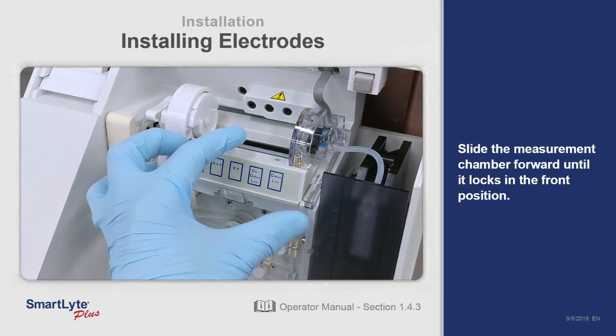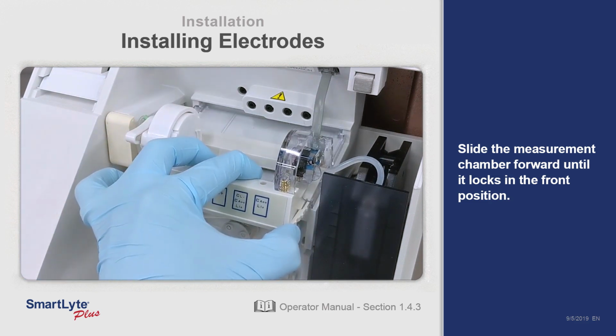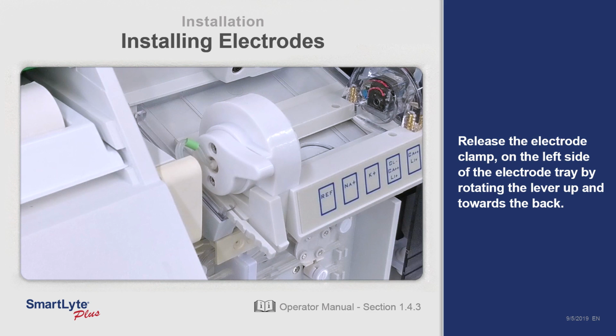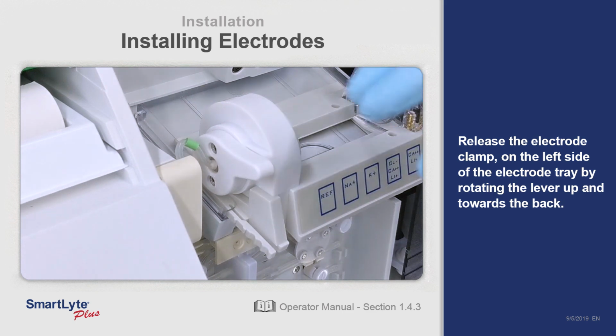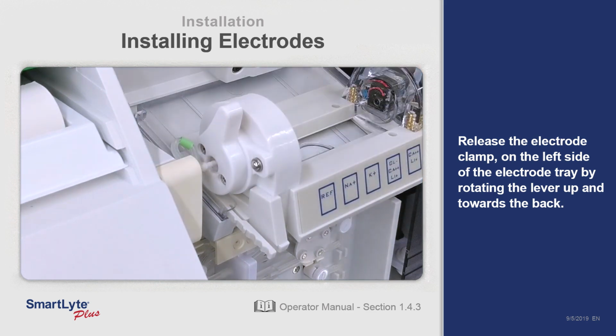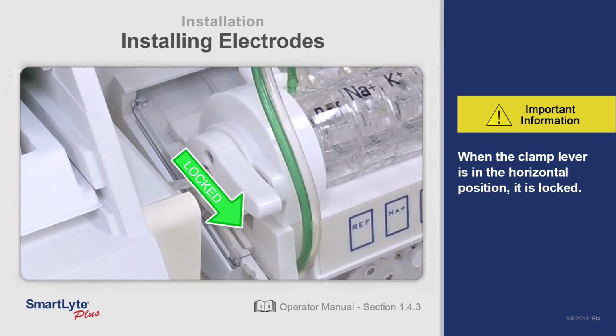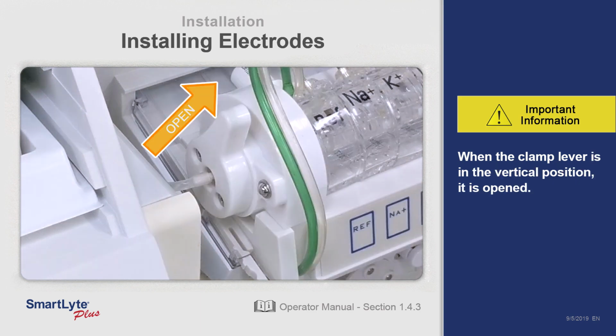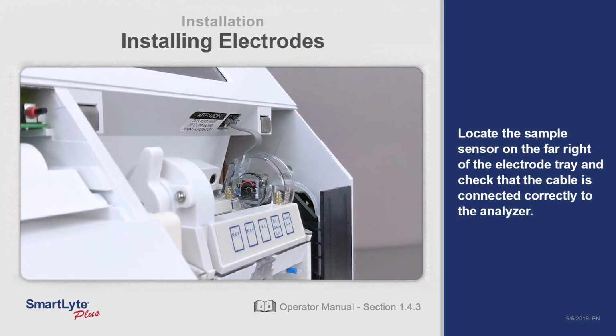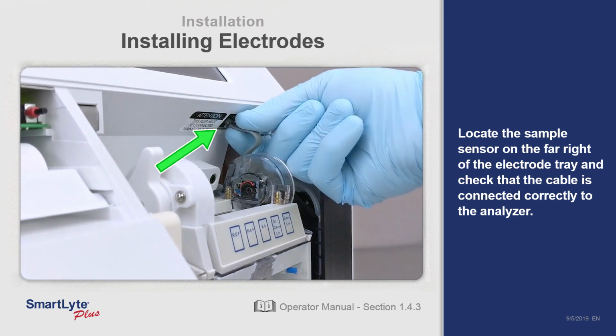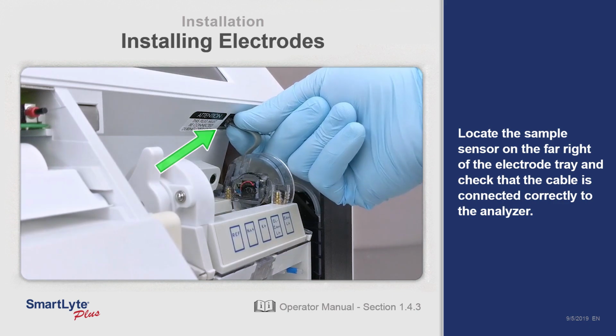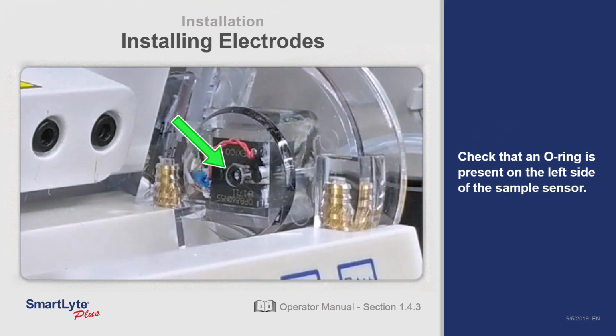Slide the measurement chamber forward until it locks in the front position. Release the electrode clamp on the left side of the electrode tray by rotating the lever up and towards the back. When the clamp lever is in the horizontal position, it is locked. When the clamp lever is in the vertical position, it is open. Locate the sample sensor on the far right of the electrode tray. Check that the cable is connected correctly to the analyzer, and check that the O-ring is present on the left side of the sample sensor.